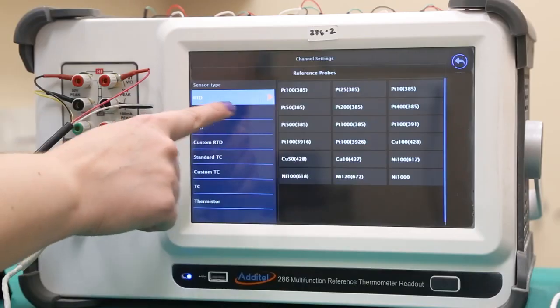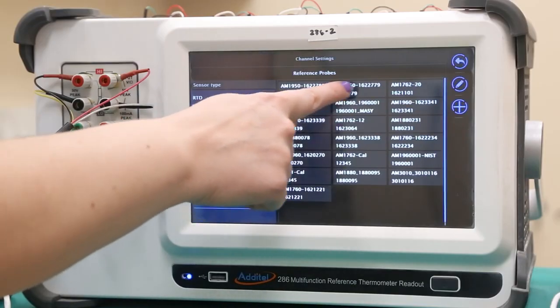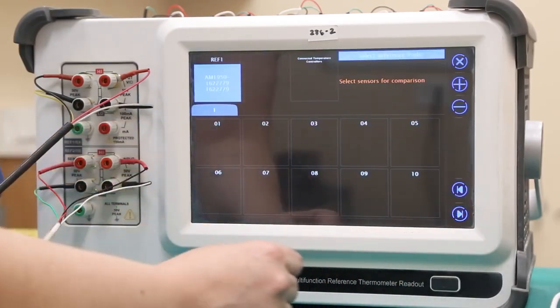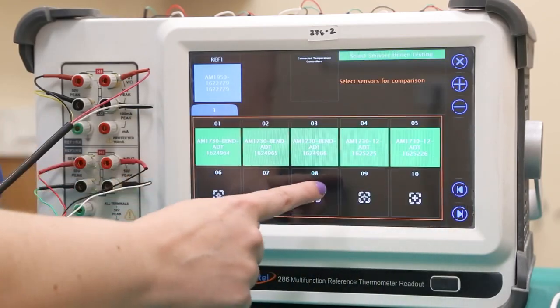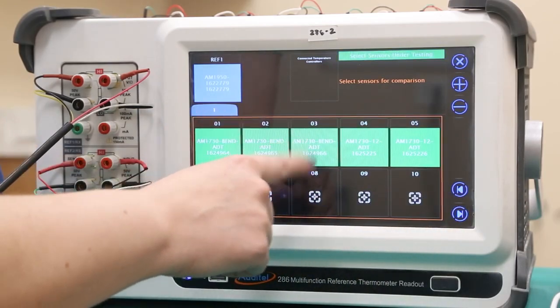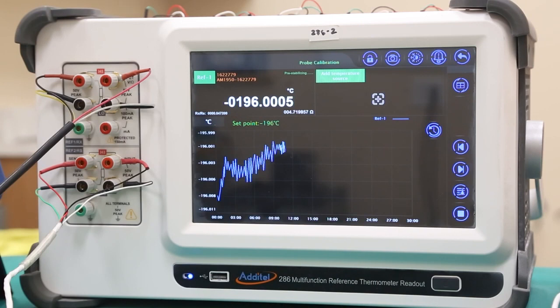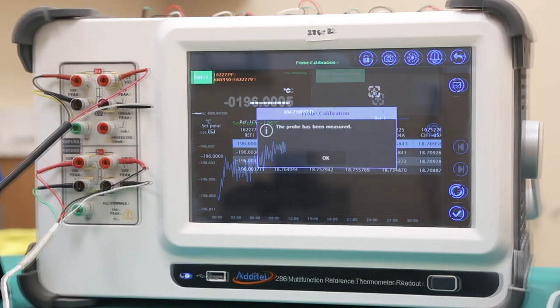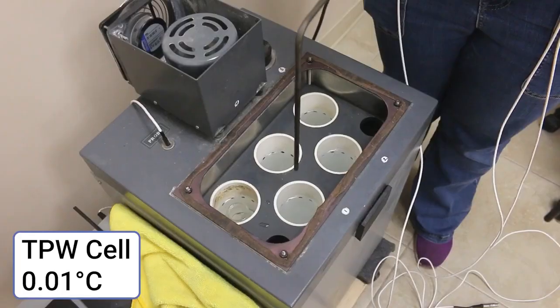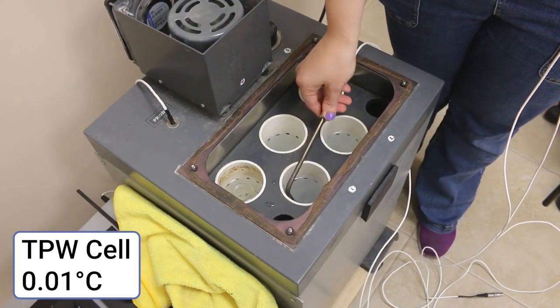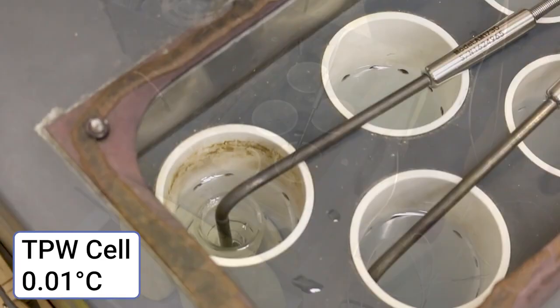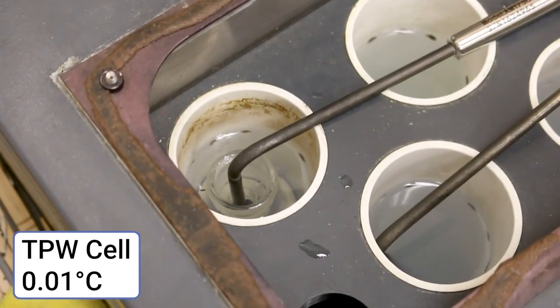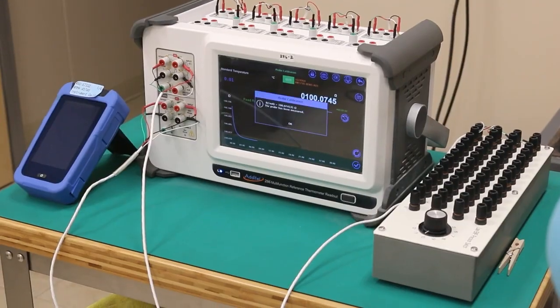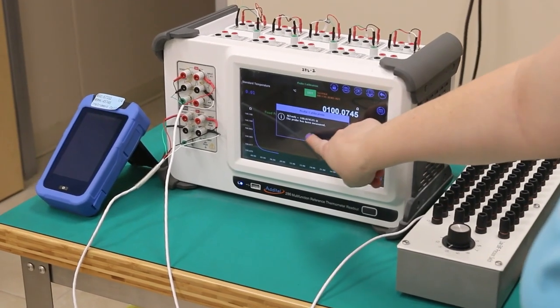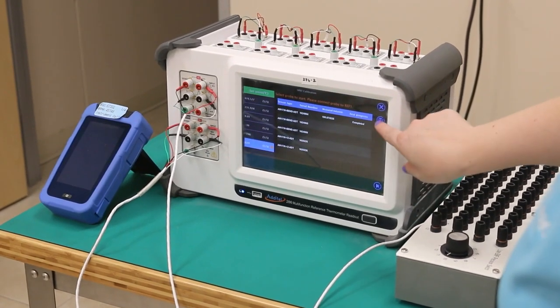First, select the type of reference SPRT, connected to REF1. Then select all of the probes, which are connected to ports 1 through 5 on top of the 286. The 286 will once again automatically measure each probe according to the test configuration set at the start of the calibration. Finally, the DUT probes will undergo one more triple point of water measurement. This will be done using the exact same procedure as previously shown in the video. In the final calculation, both triple point of water values on each probe will be averaged to ensure the probes are functioning normally across both ITS-90 subranges.